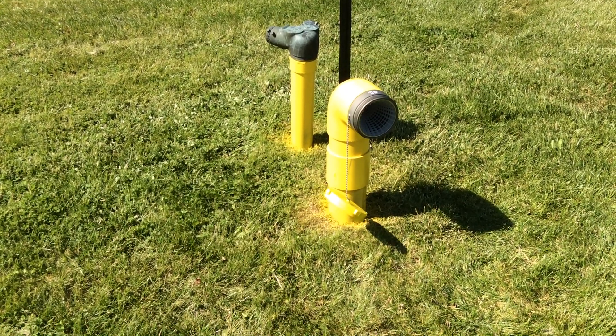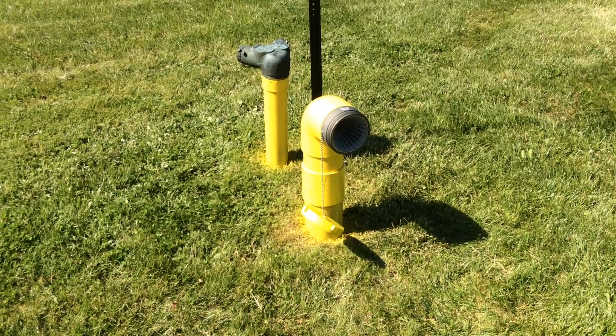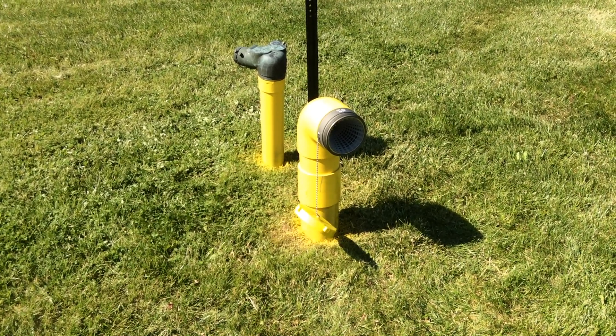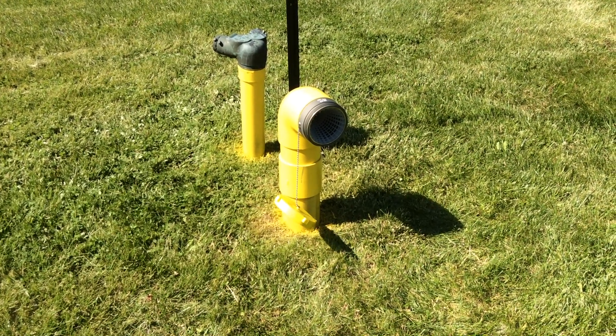Fortunately, other things weren't damaged — we just had to get a better head on. Remember, the cause of the whole problem was that somebody tried to build a dry hydrant head themselves. We generally recommend buying one from a manufacturer designed for fire department use.